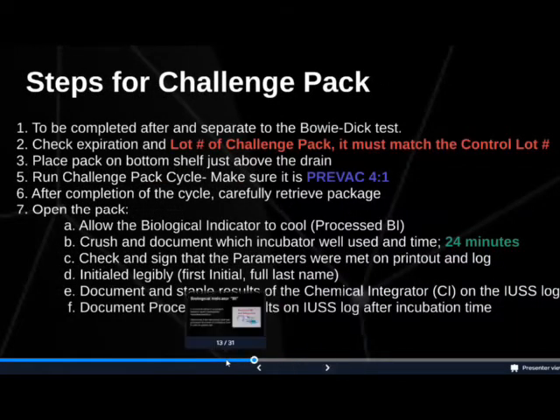So the steps to the challenge pack are to be completed after the separate Bowie-Dick test has been run and documented. You want to check the expiration and lot number, of course, and it must match the control. Place it on the bottom shelf, just like you did with the Bowie-Dick. You're going to run your challenge pack on an actual cycle, pre-vac 4-to-1. And after completion of the cycle, carefully retrieve the package because it will be hot. Again, open the package, allow the biological to cool some.